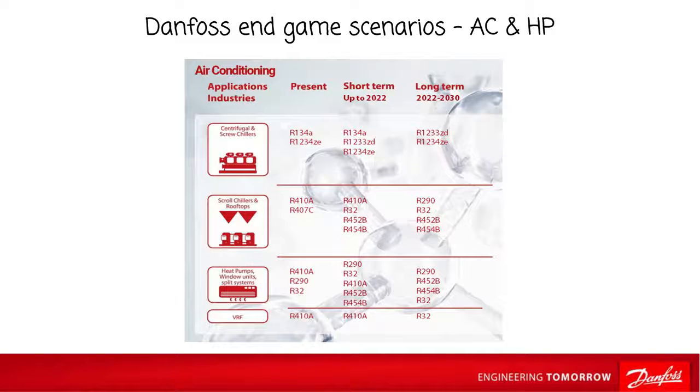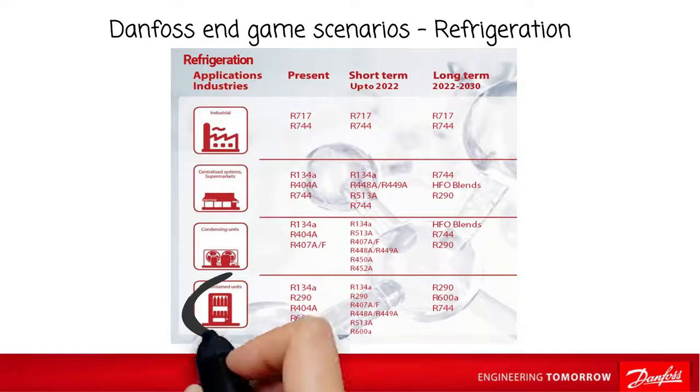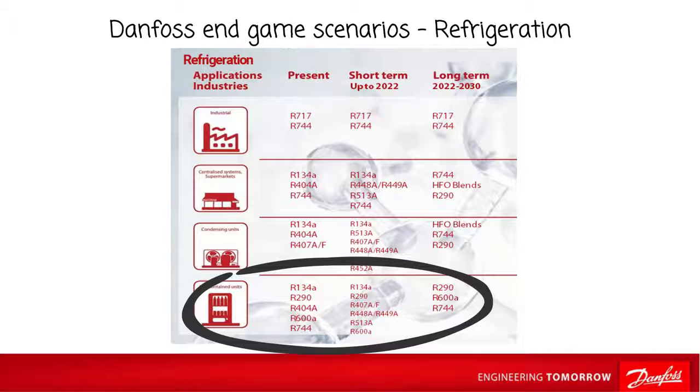solution in this area. The refrigeration sector has already used natural refrigerants for many years. If we go back to the Montreal Protocol phase-out of CFCs in the 1990s, we can see that household refrigeration was already using isobutane, an excellent refrigerant for that application and one that will continue to be used. When we look at higher capacity applications, such as vending machines, bottle coolers, self-contained units, and semi-plug-ins for retail, we see that many of these appliances use either propane or CO2.